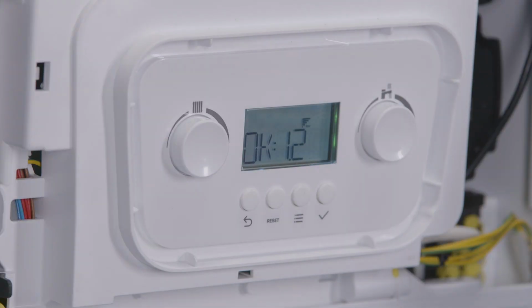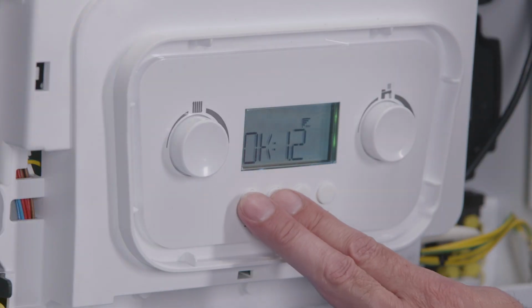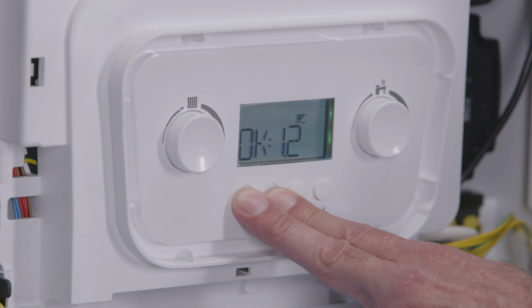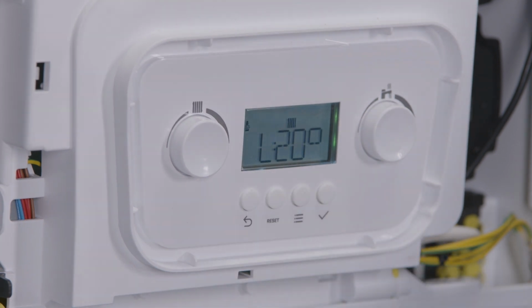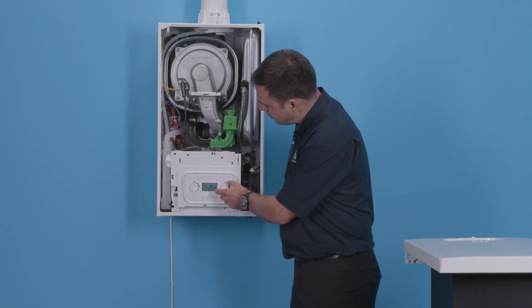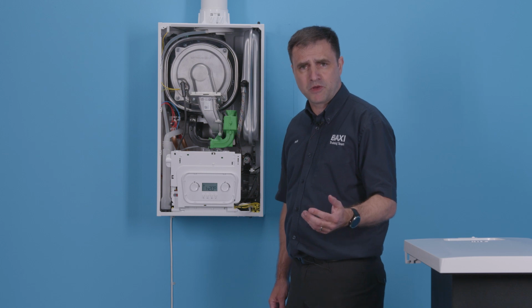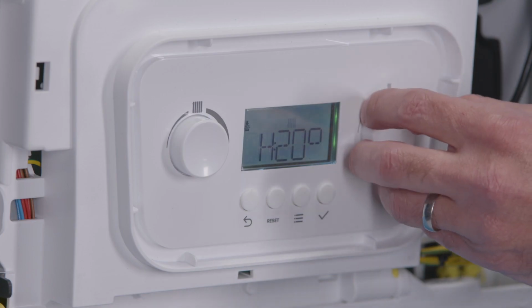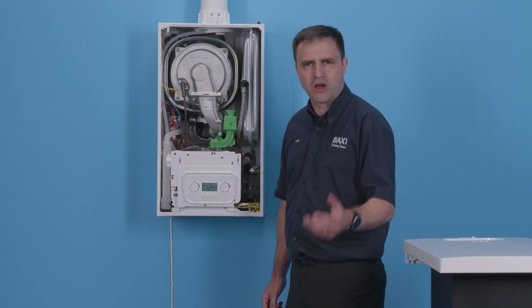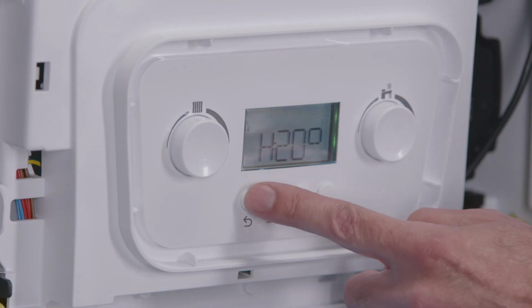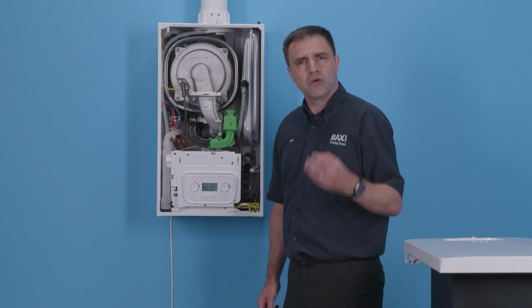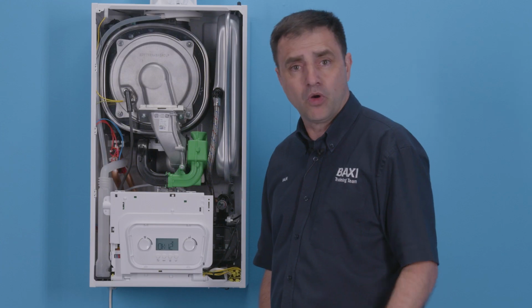To put the boiler into commissioning mode, I simply press the two left-hand buttons. On release, I'll get a capital L, which is low fire, and the boiler primary flow temperature. Either of these dials means I can move it to central heating maximum, that's the small h, or to hot water maximum, which is the large H. To come out, simply press the return button. It will last in commissioning mode for 20 minutes, or bring it out early if you want to.